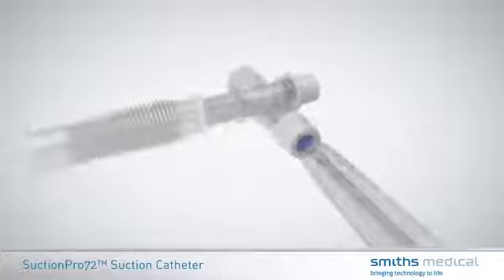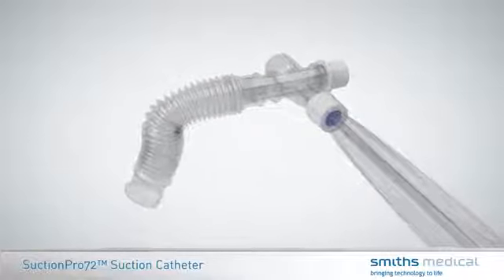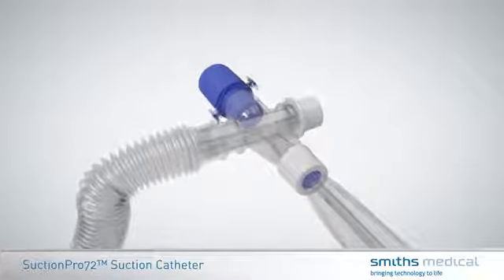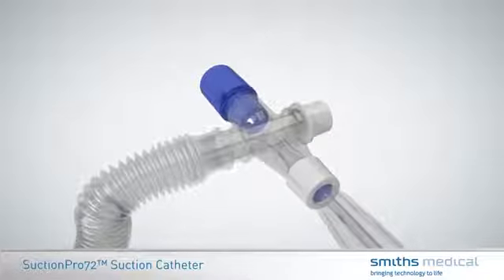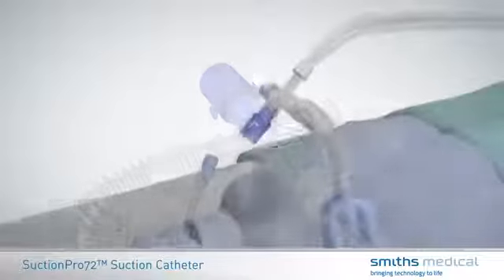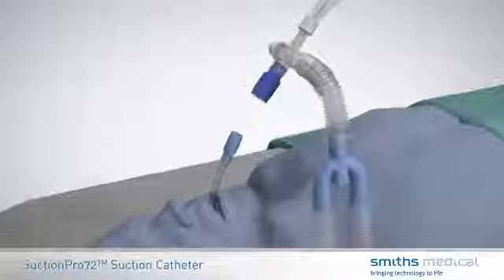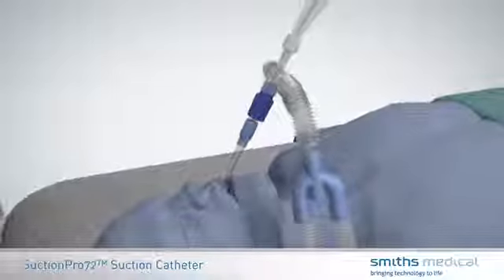Attach the flex tube to the open side port of the T-piece and then attach the ventilator circuit to the flex tube. The single-axis swivel can also be attached to reduce torque on the patient's airway. Attach the T-piece to the endotracheal or tracheostomy tube connector.